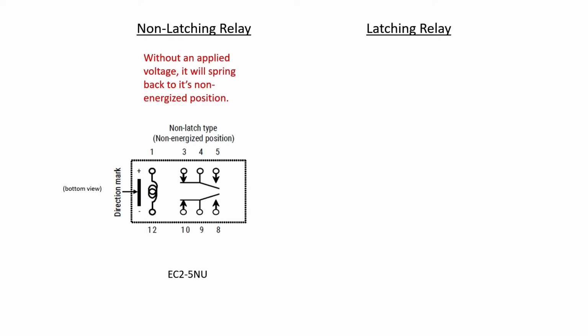The distinguishing feature of a non-latching relay is that when a voltage is not applied to the coil, the relay will spring back to its non-energized position on the high voltage side. For example, if I attach a load between pins 4 and 5, then it's going to be open until I apply a voltage between pins 1 and 12 and energize the coil. But once I remove that voltage between pins 1 and 12, pins 4 to 5 will move back to its non-energized position, which is shown here in the diagram.